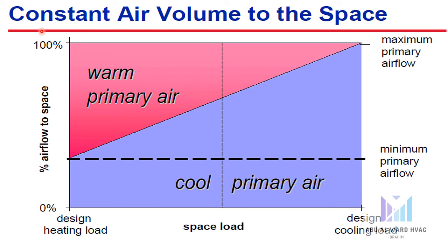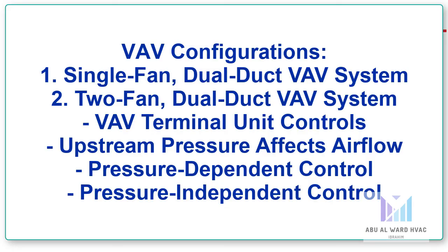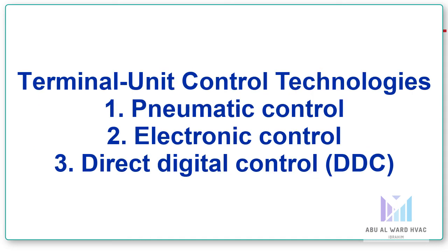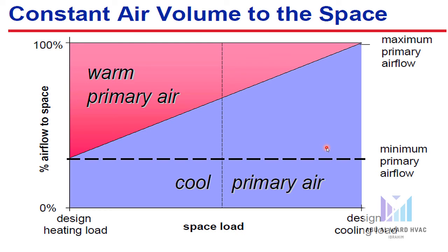The second case is the dual duct terminal with constant air volume to the space. To deliver a constant volume of supply air in a two-fan dual duct system, as the cooling load in the space decreases, the amount of cool primary air is reduced and the amount of warm primary air is increased, maintaining a constant total supply airflow to the space. Because of this constant airflow, no fan energy savings are realized at part load conditions. That's all for today's video. In the next video I will continue the remaining configurations of VAV terminals and also discuss the control system of VAV terminals. Thank you — please like, share, and subscribe to my channel.